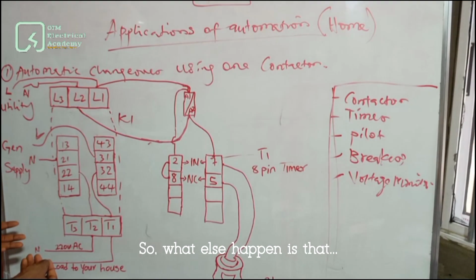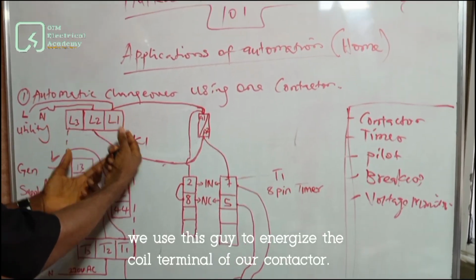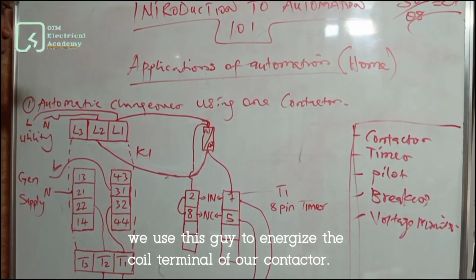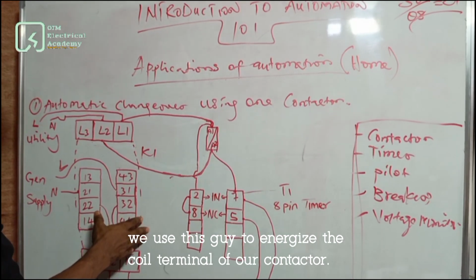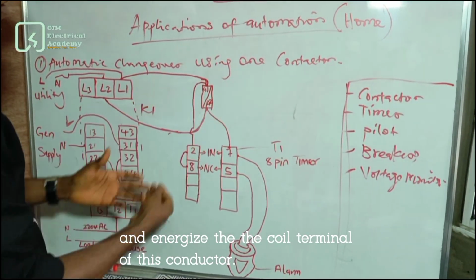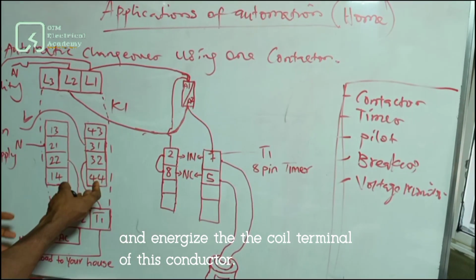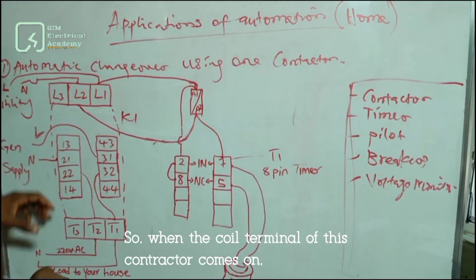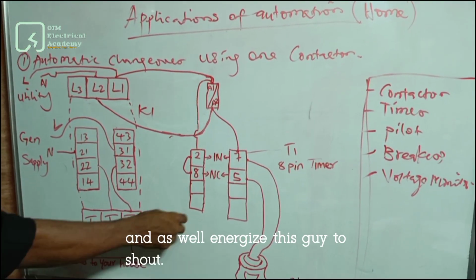What else happens is that we use this guy to energize the coil terminal of our contactor. Power comes over to this place and energizes the coil terminal of this contactor. So when the coil terminal of this contactor comes on, power goes to our load and also energizes this guy to sound.